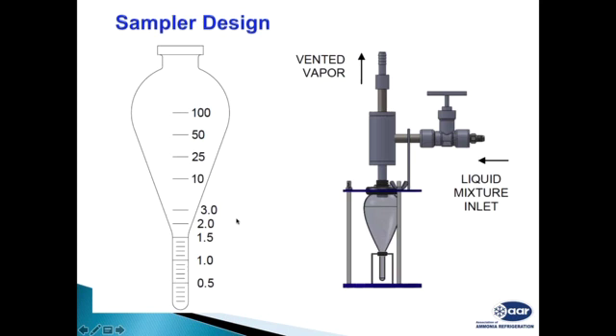Technically, you should use an automatic air purger, so it continuously purges your air. You do not want air to remain in a system. Air is like a passenger traveling in a train without a ticket. It does not contribute anything to the income of the train. Because of the air, it does not condense, does not evaporate, does not generate any refrigeration effect. Your electricity consumption increases and your refrigeration capacity decreases. You should purge continuously; automatically is the correct solution.